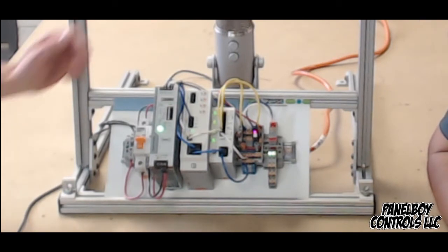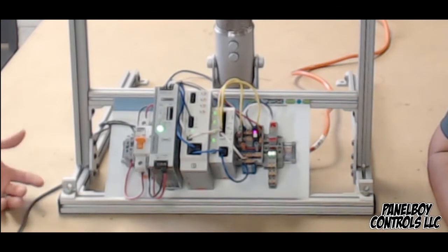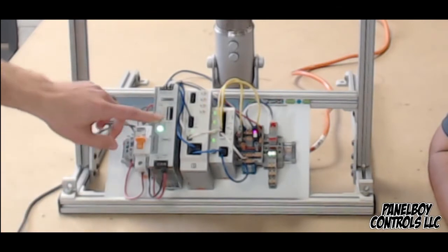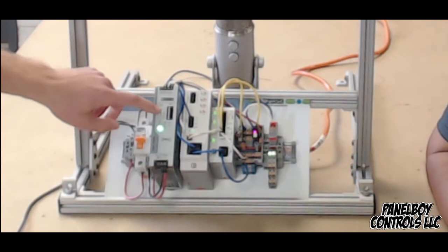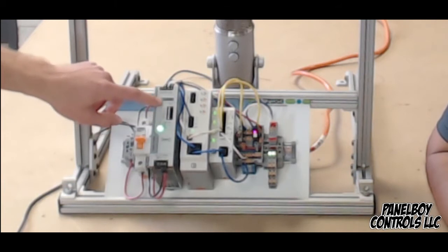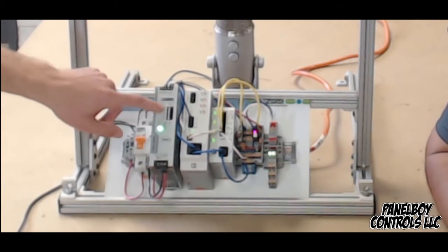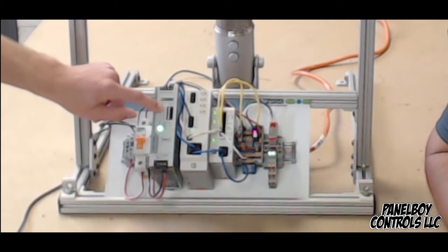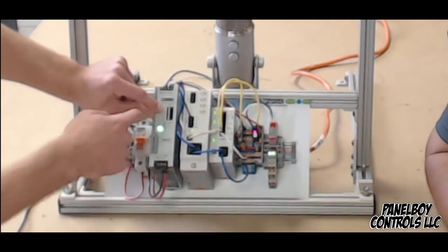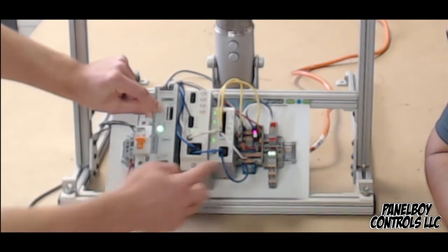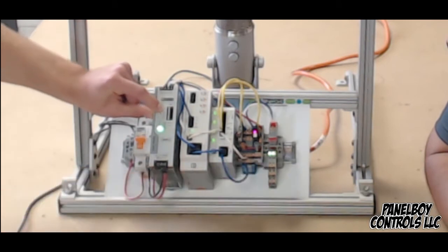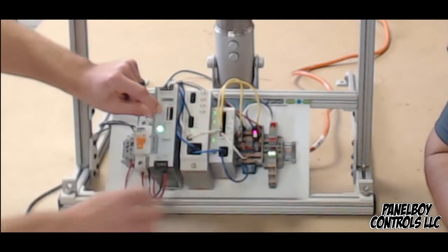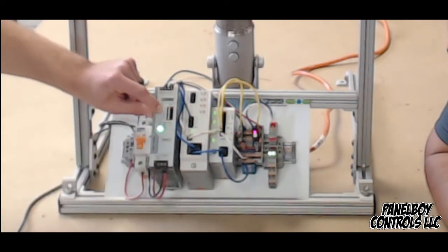The one on the left here is NEC class 2, which is current limited under 100 watts. To demonstrate that, this power supply has some parameters I can adjust just by pressing this button. When I get above 27 volts, it will shut down because it wants to stay under 100 watts, and you'll see this LED go red soon.